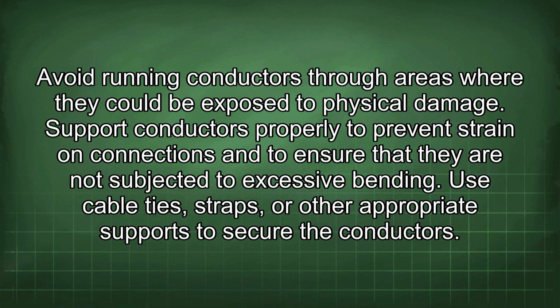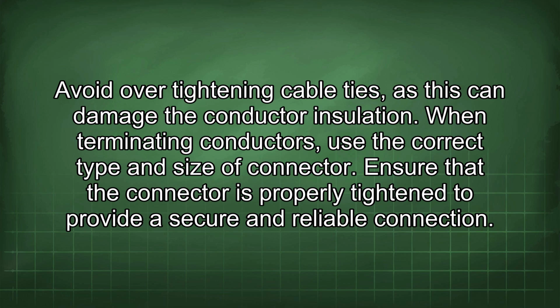Avoid running conductors through areas where they could be exposed to physical damage. Support conductors properly to prevent strain on connections and to ensure that they are not subjected to excessive bending. Use cable ties, straps, or other appropriate supports to secure the conductors. Avoid over-tightening cable ties, as this can damage the conductor insulation.